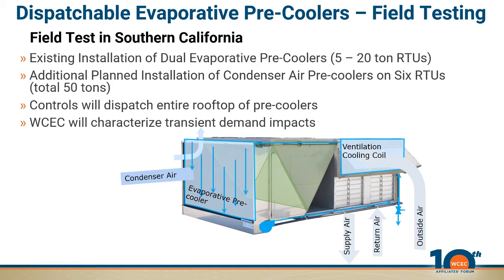As a rough estimate, it should be about a factor of two. So when you turn on the water, the power draw goes down by some amount and the capacity goes up by some amount — those percentages are on the order of 1% per degree F for each, maybe 0.75%.